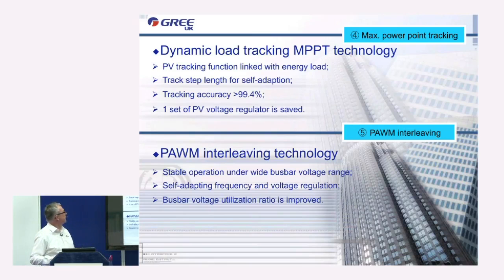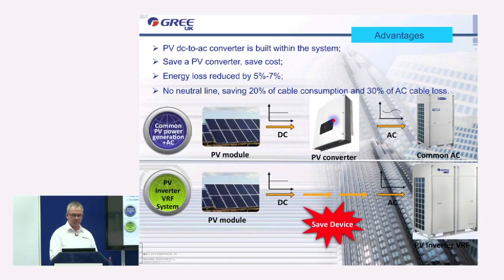The MPPT technology, so tracking function, is built into the system, linked with the energy load. So this means if the machine needs a bit more power from the solar, it will track the DC voltage, the power generated, to determine where's my maximum power point, where's my most efficient power point. Is the solar panel providing that? If the solar panel is providing it, it will take it. If the solar panel isn't, due to a sunlight issue, then it will take it automatically in real time from the grid. Very controllable.